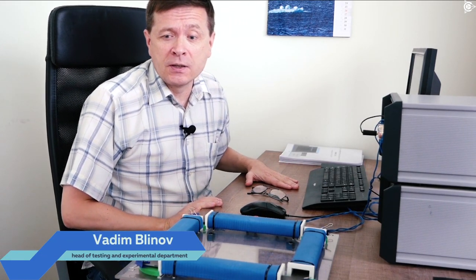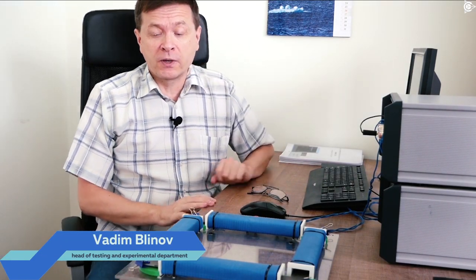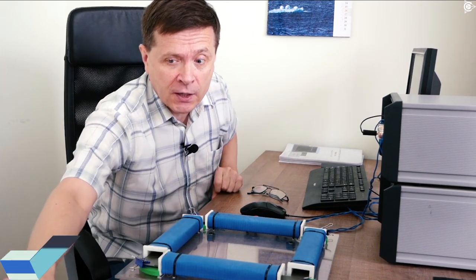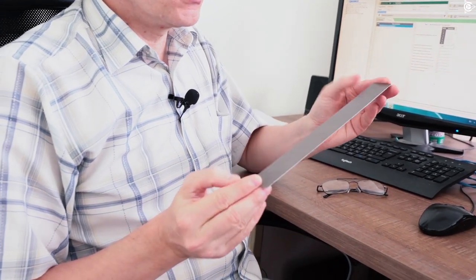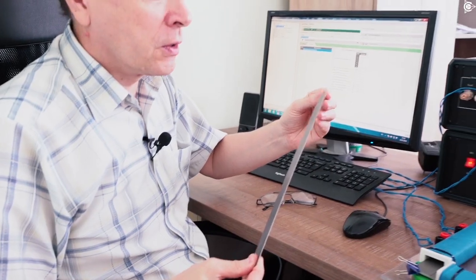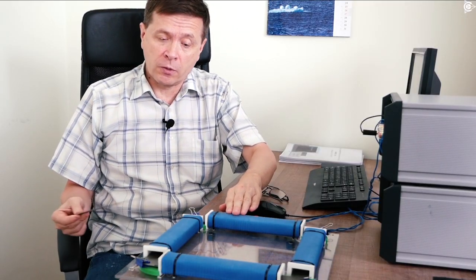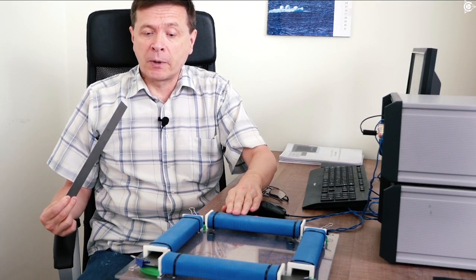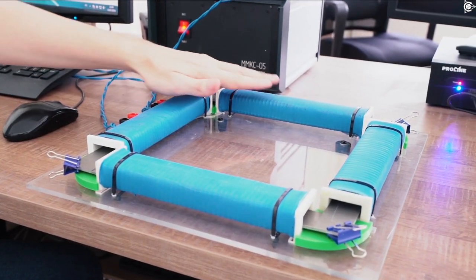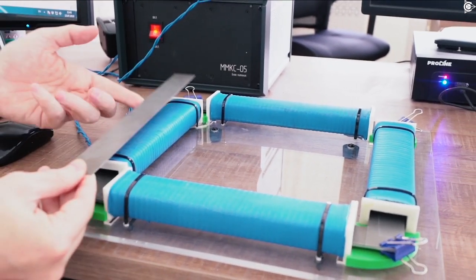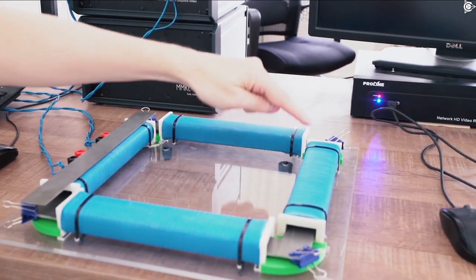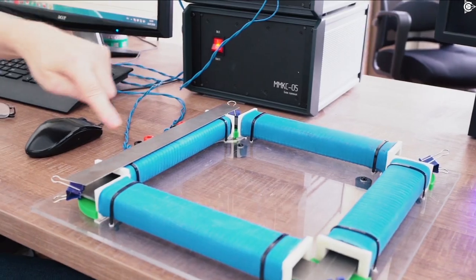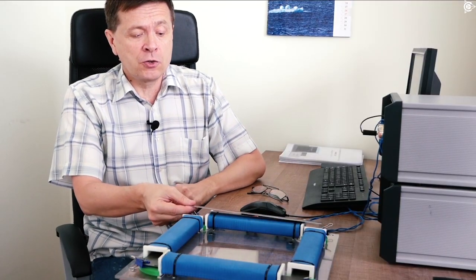For studying and measuring the properties of electrical steel, the steel is cut into such samples and put inside the magnet units mounted in this machine. Let's make a closer view. It's called the Epstein machine. It consists of four magnet units, inside which our plates are inserted and thus form a closed core.